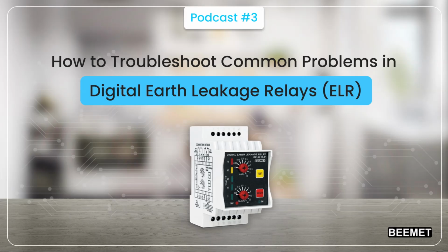When to replace versus repair digital ELRs. Small concerns like wire cuts or calibration errors can be fixed with repairs. Bigger issues like broken processors or weak CTs require newer parts. Even the age of the relay also matters. When safety is in jeopardy, replacement helps reestablish trust. This will aid in electrical equipment maintenance over time.